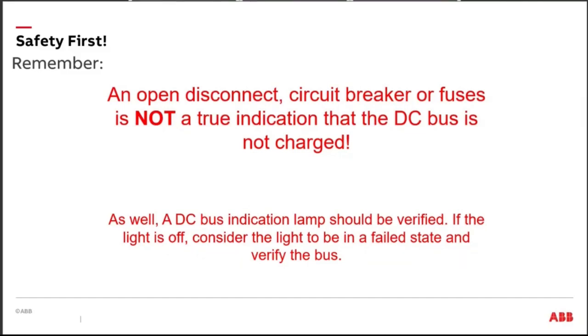You want to have a meter and you want to know how to use the meter. You want to look between your positive and negative bus and make sure that you don't have a charge on your DC bus. I kind of joke and tell people, if you don't smoke, it's a good time to start. Turn the drive off, go out and have a smoke, come back in, check your bus. You need to give it 2 or 3 minutes, sure enough. Let the DC bus discharge.